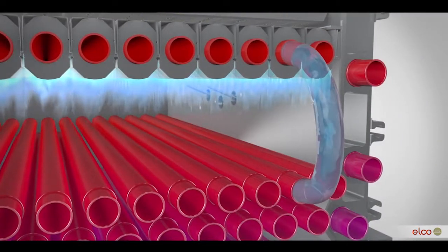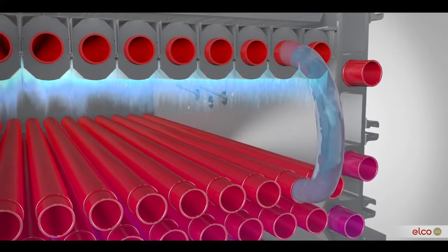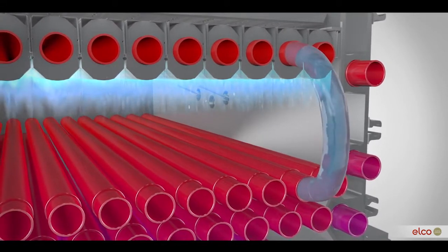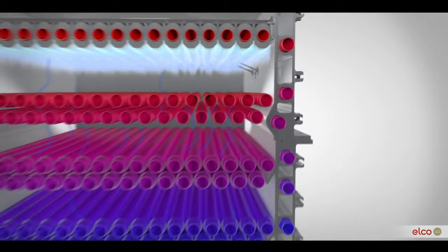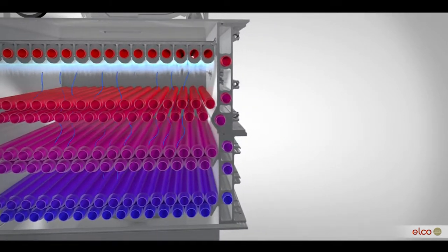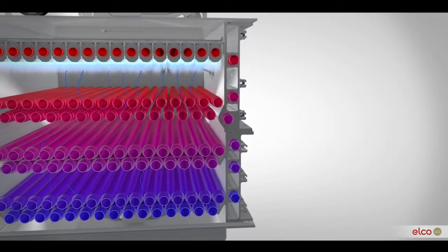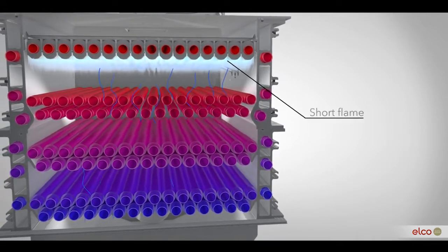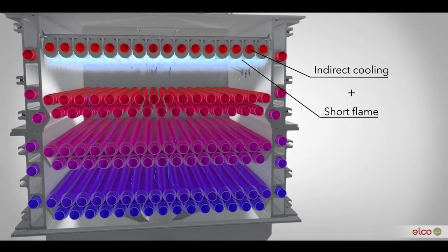The heating water passes from the heat exchanger through the burner, creating an indirect cooling effect on the flame and reducing the flame temperature. By cooling the flame, the reaction between nitrogen and oxygen is limited.